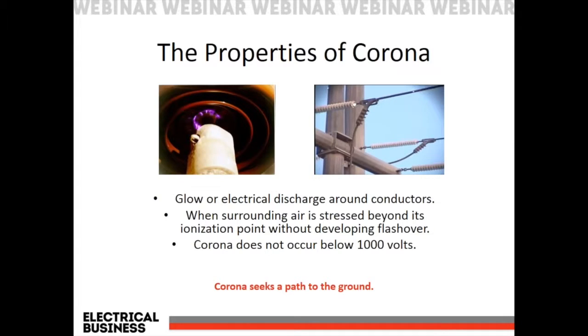With corona, and as I said, when I talk to people, I go to a lot of facilities, and electricians are obviously thinking corona is our beer, so we're hearing beers, or seeing beer, or whatever the case. That's not the case in the electrical world. Corona is basically a low-level electrical discharge around conductors. It happens when the surrounding air is stressed beyond its ionization point, but it doesn't develop flashover. So what we're seeing here is just a complete ionization occurring, and from there, we were able to hear that.